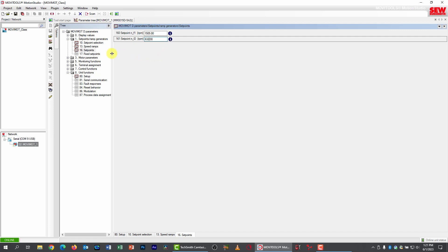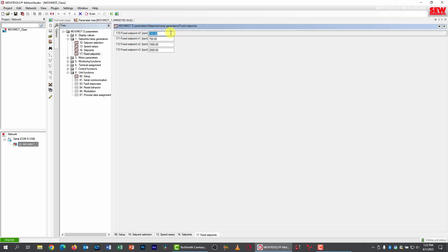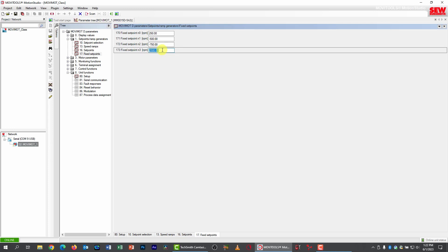These values correspond to what the F1 and F2 dials would set, but we're going to key in actual values. Just to prove we can set precise speeds, I'll change my first speed from 1,500 RPM to 1,505 RPM, and my second speed to 632 RPM — that shows we have fine control of the speeds. Notice there are decimal values too, so you can go down to fractional RPMs. I'm also going to set my fixed set points for the alternative binary mode, so let me set all four speeds.